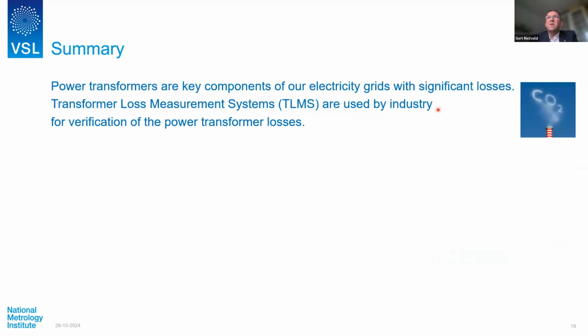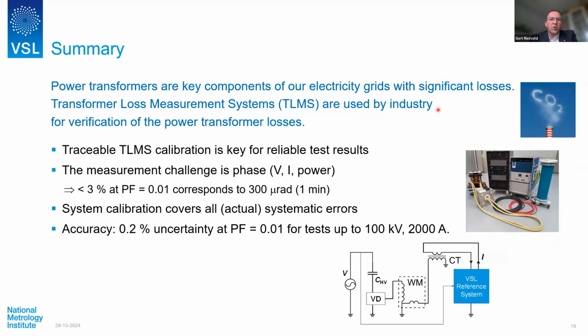With that, I come to an end. Power transformers are key components in our grid with significant losses, and the industry is using loss measurement systems to verify these losses. And of course, you need a calibration in order to make sure that this loss measurement is really reliable. Measurement-wise, the key challenge of this particular calibration is phase. And the 3% is a requirement from IEEE. Via system calibration, we are able to get to the 0.2% uncertainty at this power factor, which is really needed by the most high-end power transformer manufacturing industry.